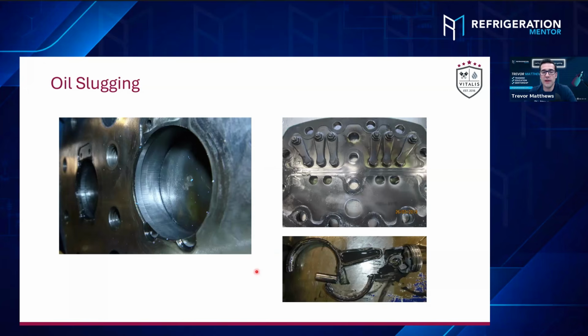Yeah, for sure. And if you pull off a head, just like Jonas said, and that is full of oil, your head's not supposed to be full of oil. It doesn't compress that stuff. So you've got to figure out, how did it get there? What caused it? Is it the rings? Is it the discharge damage? Is there something else going on? Because they don't compress liquids. So it should not be full of oil.